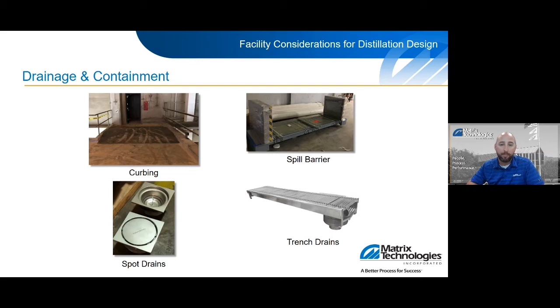Second picture, top right, is the spill barrier. What I like about this device, well, let me explain how it works. There's a sump system inside of there that will detect the liquid fill up, and it's a spring operated door that comes up. This system is great for containment walls and allows you the flexibility to drive equipment in and out of there without bringing in a large lift to lift a fork truck or a scissor lift into place. So this gives you the ultimate flexibility. They are a little costly, but they definitely save some headaches down the road when you need to get into that space again. And then you've got spot drains and trench drains, pretty typical installations for most facilities.